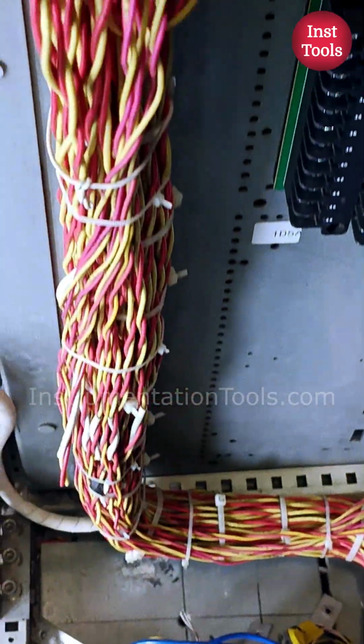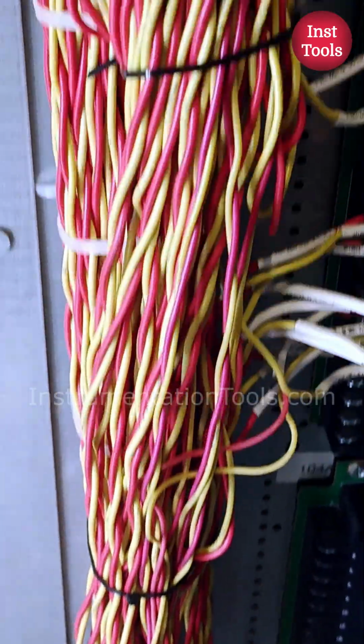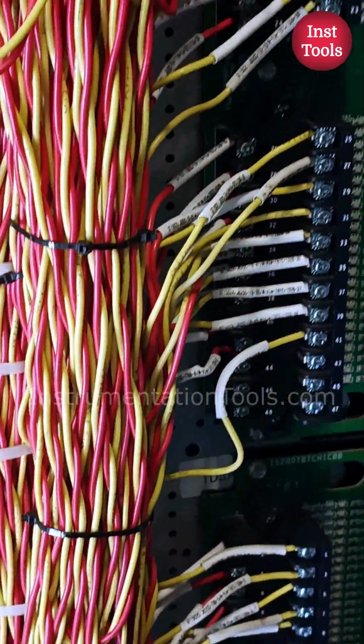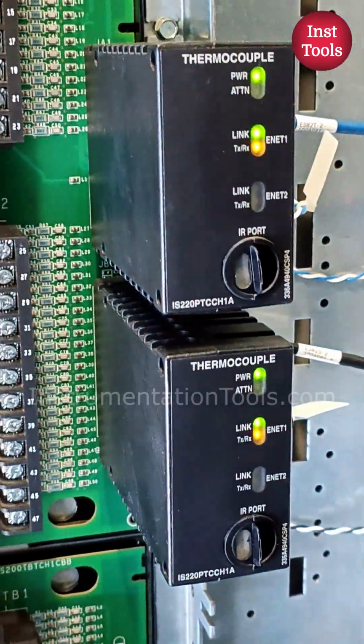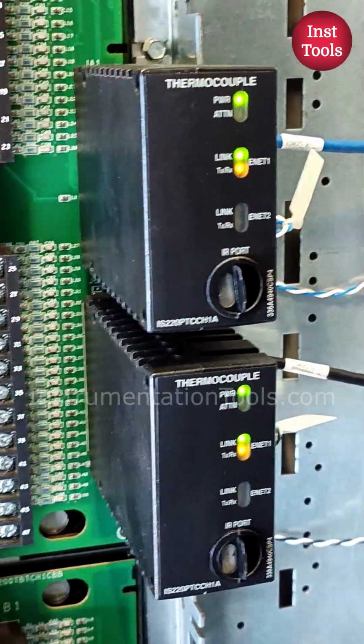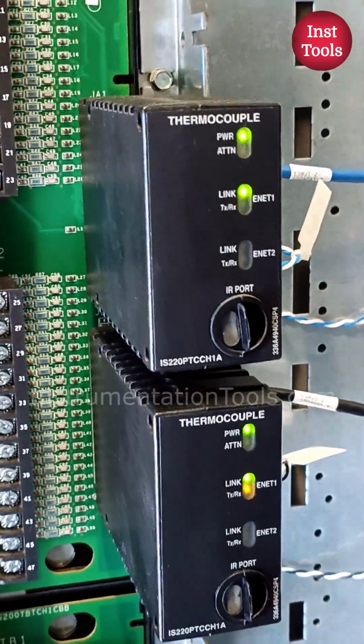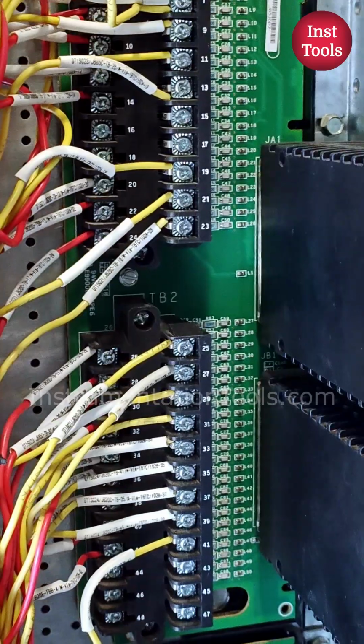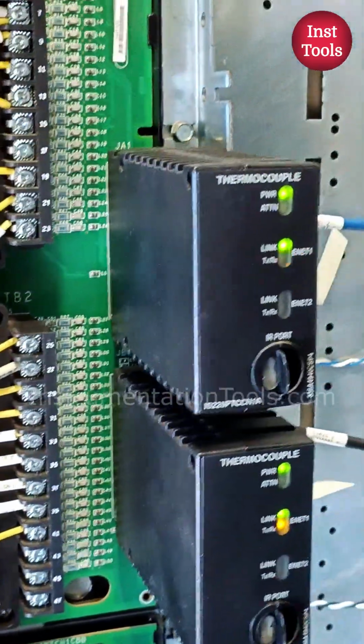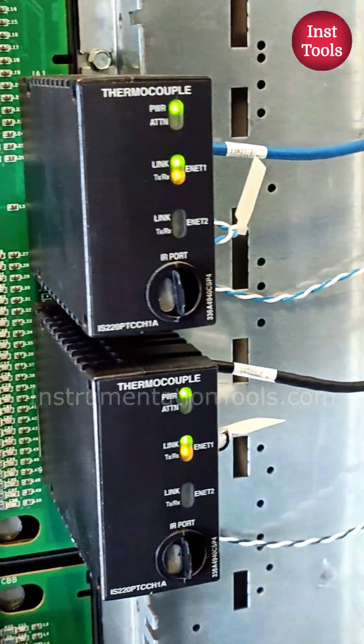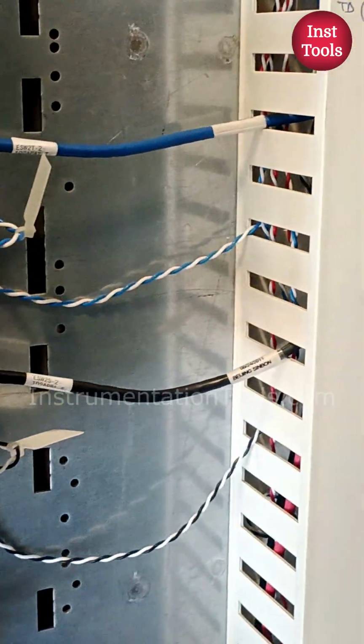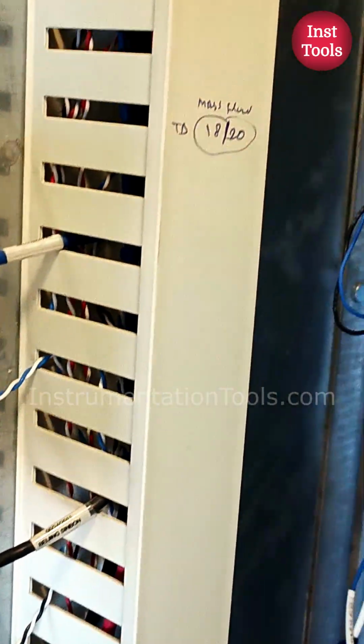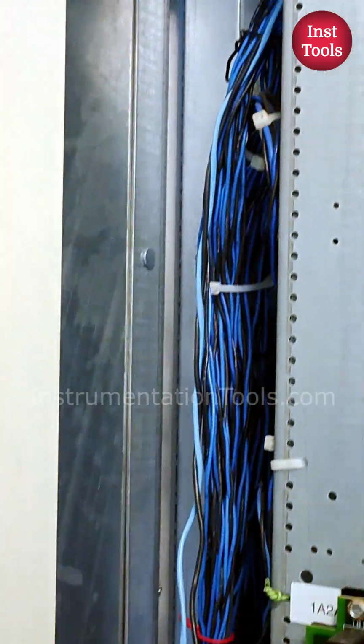These are the thermocouple cables coming from the gas turbine and connected to the thermocouple I/O pack. This thermocouple module processes the received voltage signal and calculates the equivalent temperature value. And using Ethernet cables, the data will go to the controllers via IONET communication.